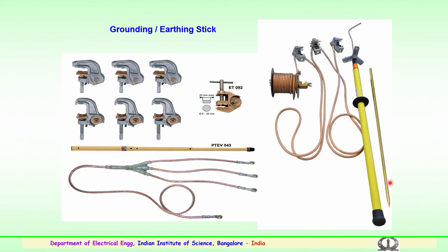So, these are a few examples of the grounding stick or the earthing stick. Here, this thing will be connected to the grounding stick. The grounding stick is the metal part which will be connected to the ground wire, and subsequently it will be grounded, a connection to the ground. So, this comes in contact with the equipment which is to be grounded. So, this is an example of the substation earthing stick or grounding stick which is used for maintenance by the personnel. So, thank you. That was about the importance of grounding and the safety precautions to be employed by the personnel who are working in substations. Thank you.